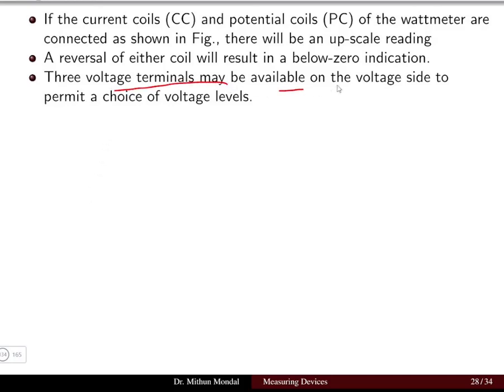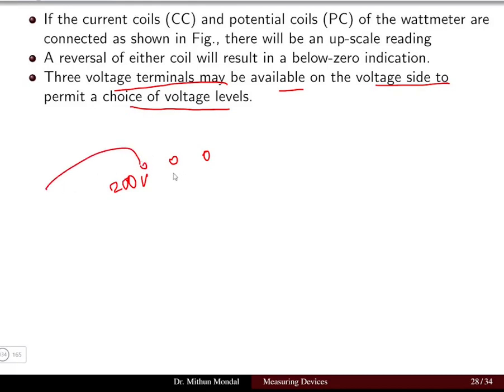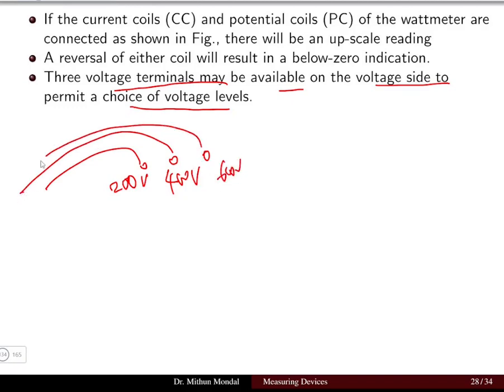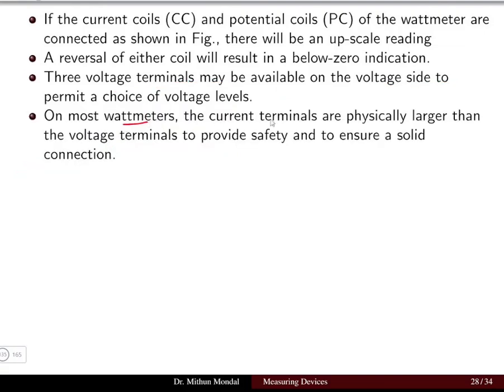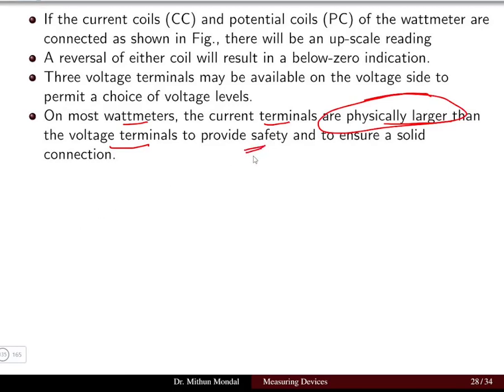Three voltage terminals may be available on the voltage side to permit a choice of voltage level — for example, 0 to 200 V, 0 to 400 V, or 0 to 600 V. On most wattmeters, the current terminals are physically larger than the voltage terminals. The current coil is larger than the voltage coil to provide safety and ensure a solid, proper connection.